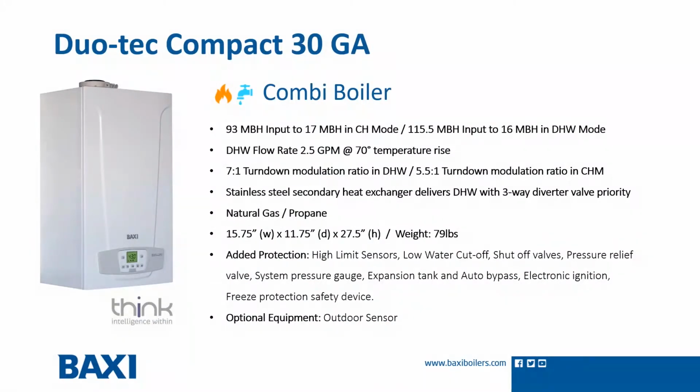The GA30 is our smallest residential combi boiler. At 93,000 BTUs of input to 17,000 BTUs on central heating mode, and 115,000 to 16,000 in domestic hot water mode. This unit will produce 2.5 gallons a minute at a 70-degree rise in temperature. That means that this would be good for a 1-bathroom home with normal fixtures.